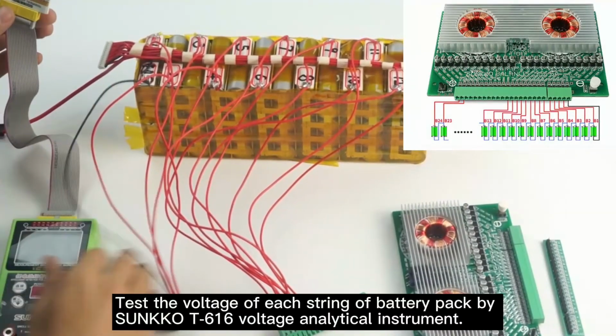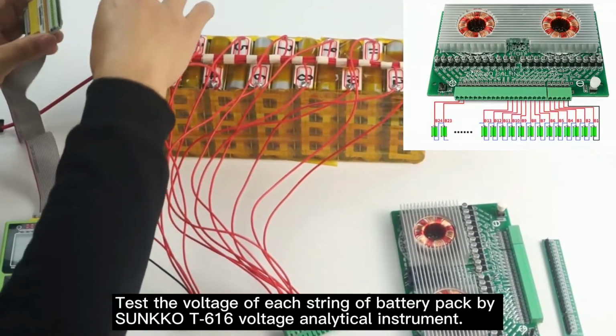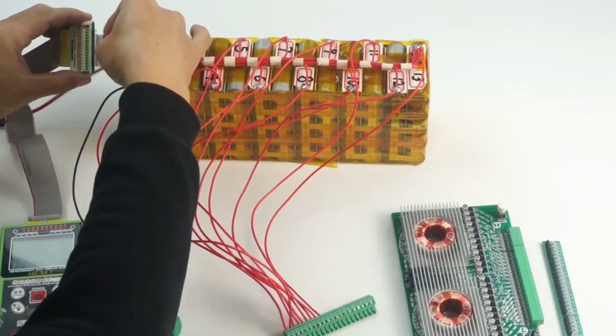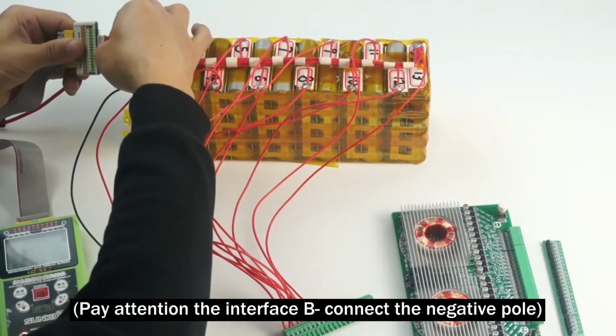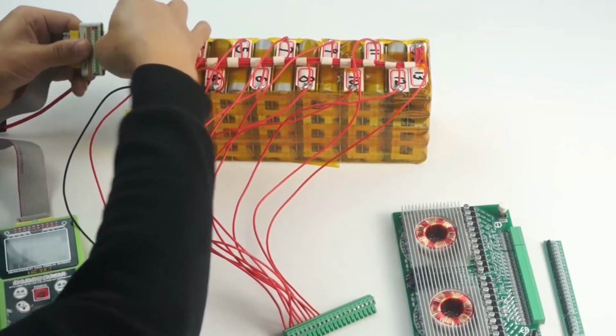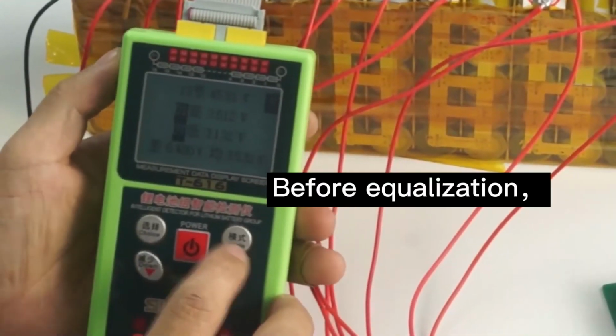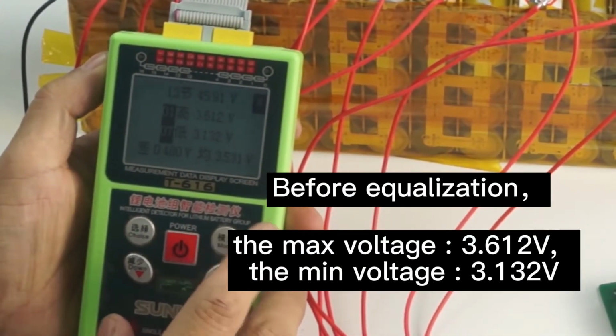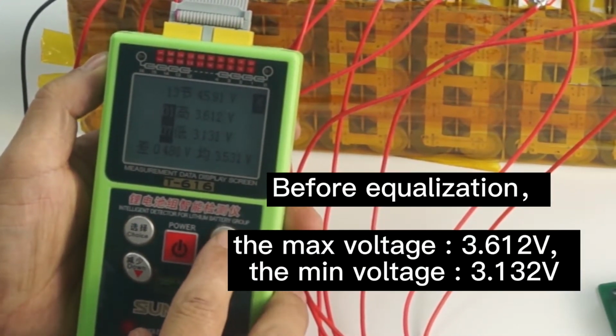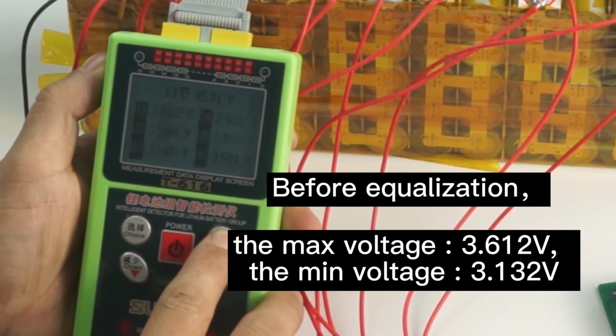Test the voltage of each string of the battery pack with the Sunkko T616 voltage analytical instrument. Pay attention: the interface B- connects the negative pole. Before equalization, the max voltage is 3.612 volts, the min voltage is 3.132 volts.